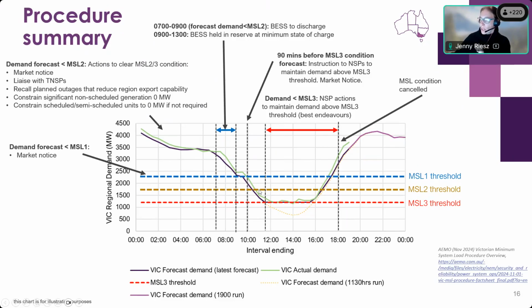If we fall below the MSL2 condition, the batteries will sit close to empty at their minimum state of charge, ready to ramp up as a load if need be, because it takes about 90 minutes to activate active PV curtailment. As mentioned earlier, there's an obligation to return to secure, or use best endeavors to return to secure, within 30 minutes. So we cannot bring online that active PV curtailment quickly enough to achieve that. We use the batteries as a stopgap measure to ramp up as a load very quickly and buy us time to return to secure by bringing online active PV management if that contingency occurs.